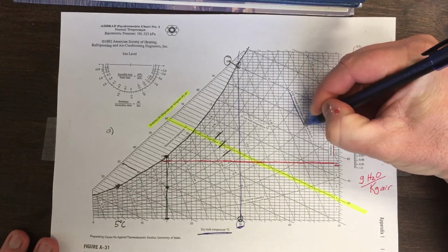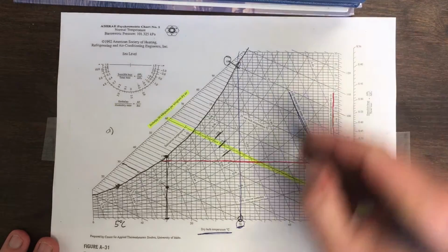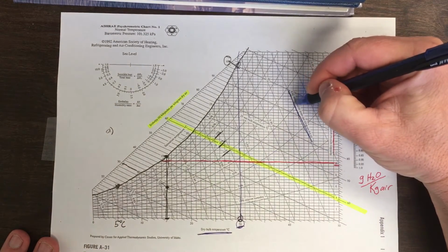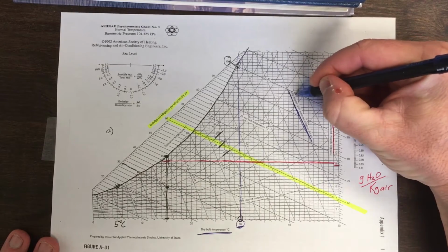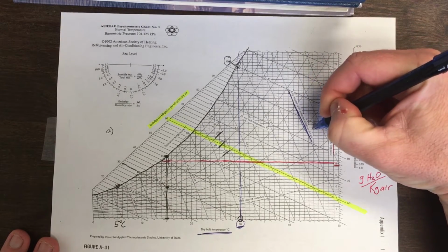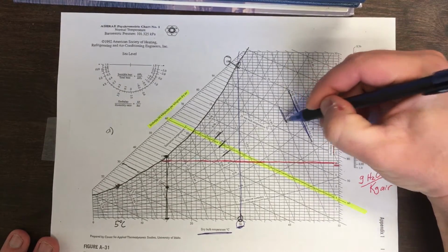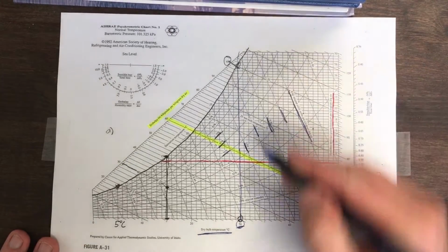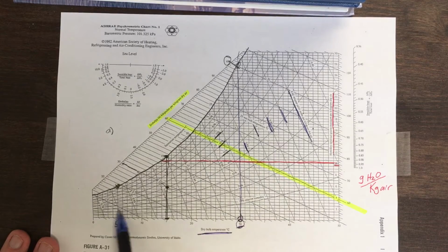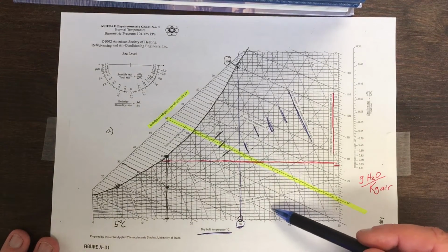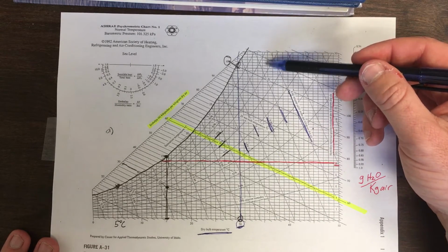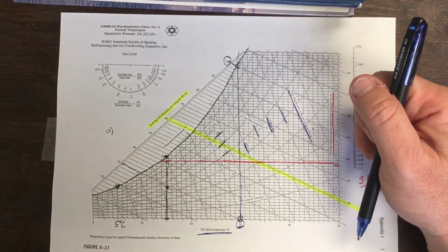Specific volumes have this steeper slope than the enthalpy. So enthalpies have this slope, specific volumes have these slopes. So there's 0.92 cubic meters per kilogram, and then there's an unmarked one, and then there's 0.9, unmarked, 0.88, all the way down. So you can see the colder air is more dense, has a lower specific volume, and with greater humidity you've got higher specific volumes also.